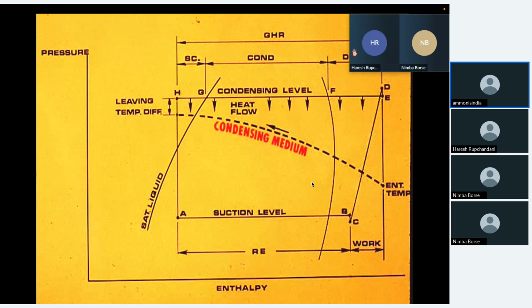But in an ammonia plant, generally we rarely use subcoolers, because the moment we use a subcooler, it leads to an increase in superheat, and the gamma, the compression index of ammonia, is very high, so it leads to very high discharge temperatures. So as far as possible, we don't use suction liquid subcoolers in ammonia plants. But remember, this line is very important. I will tell you my experience.